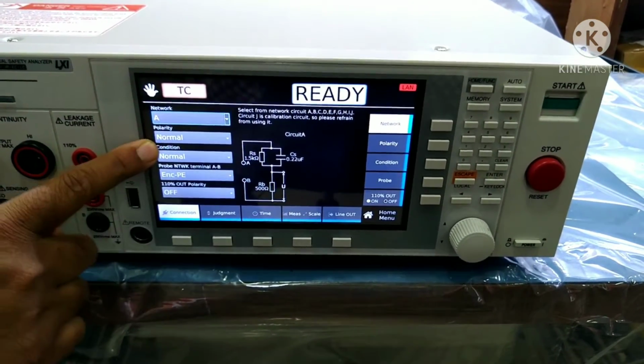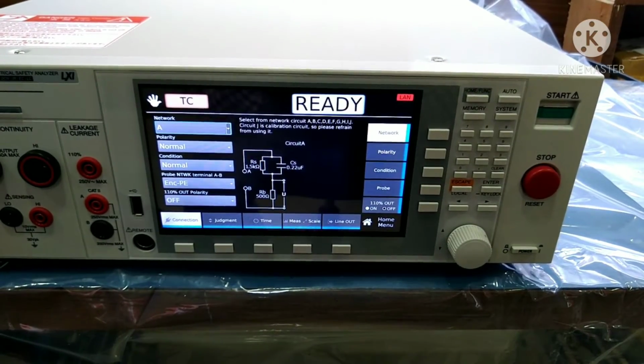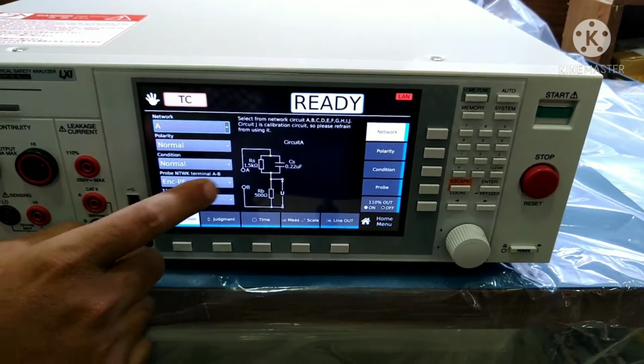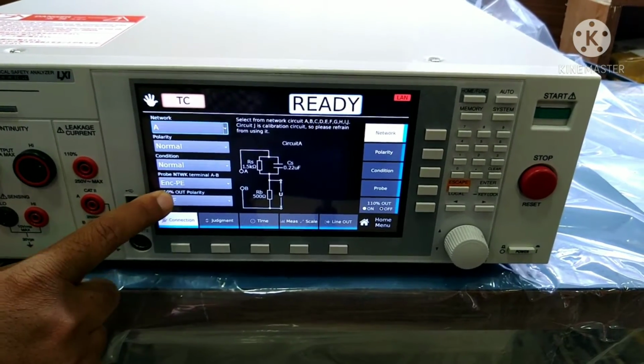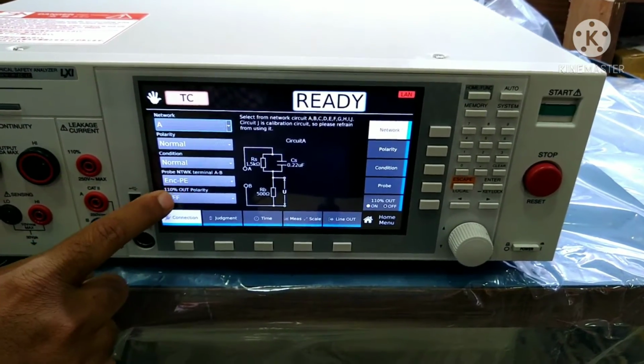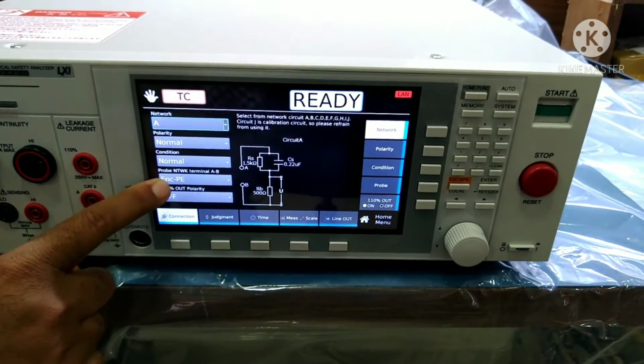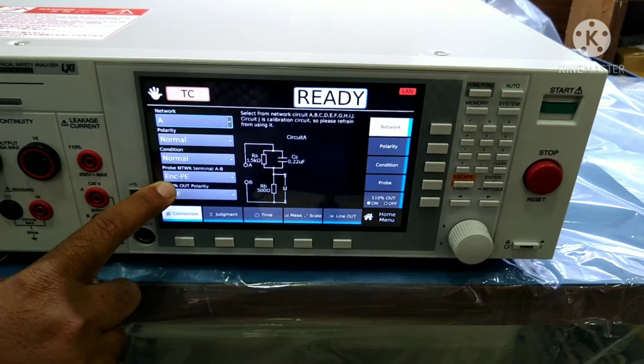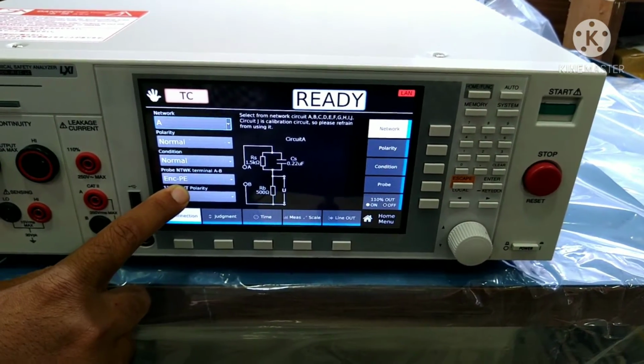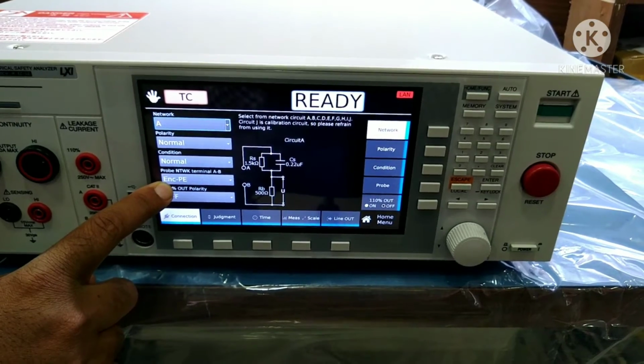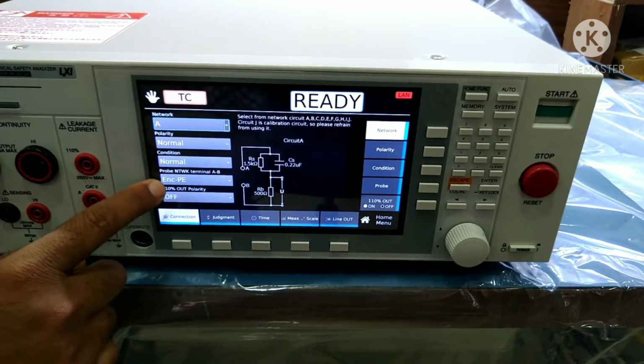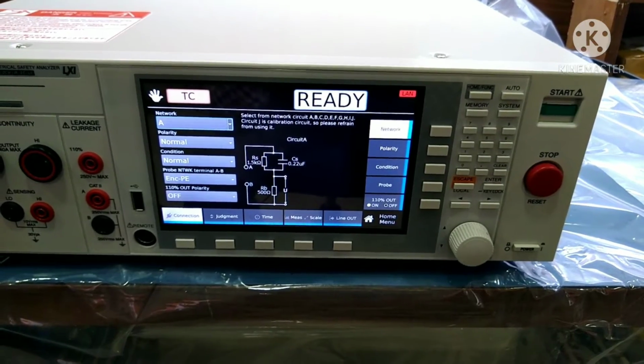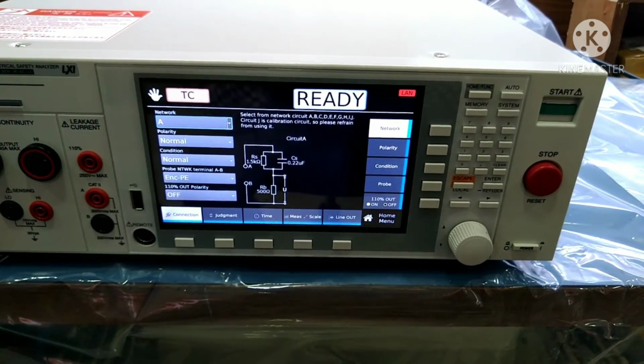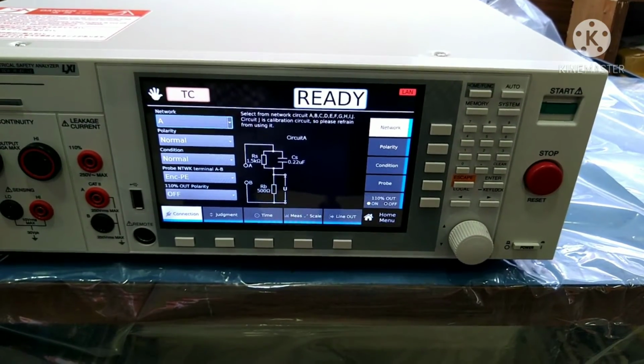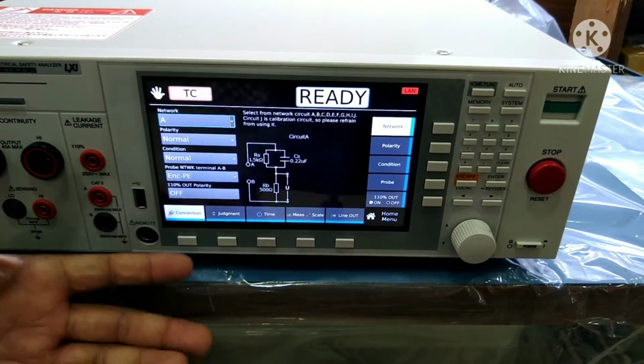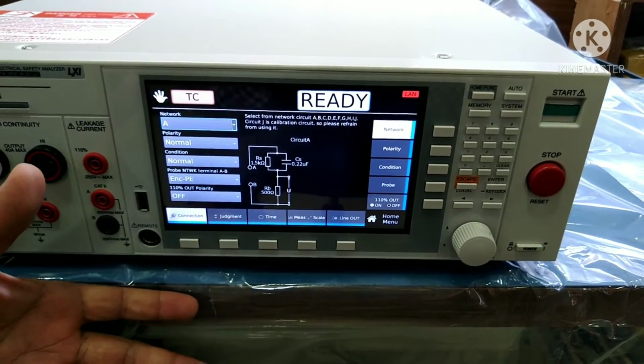Polarity, you can also change the polarity between your output sources. Conditions, probe position, like which part you want to check the leakage, like enclosure to PE. Enclosure will be the outer part of any DUT, device under test, and PE is the protective earth. So in this setting we will check the leakage between the enclosure and the protective earth. Whatever judgment comes, it will show here. In the open condition it will show, because right now we are only discussing the basic settings of this TOS9303LC.